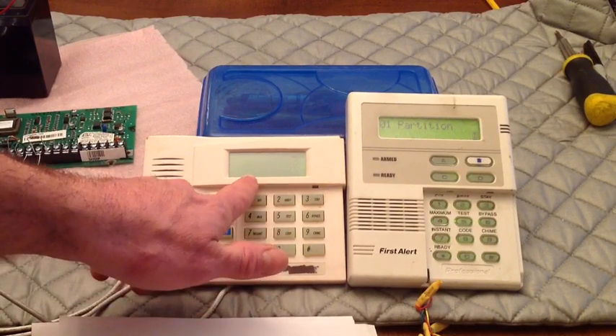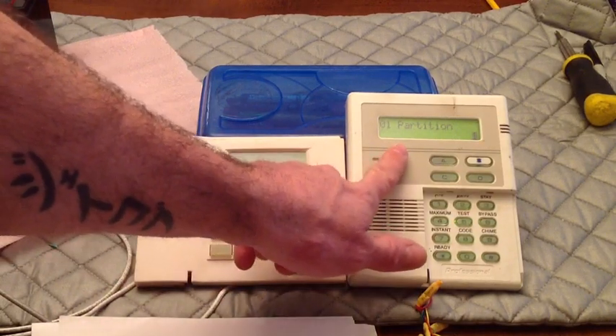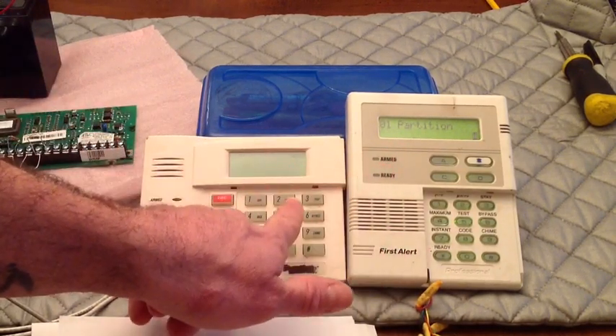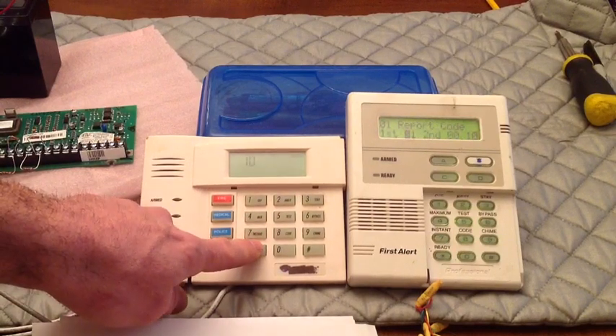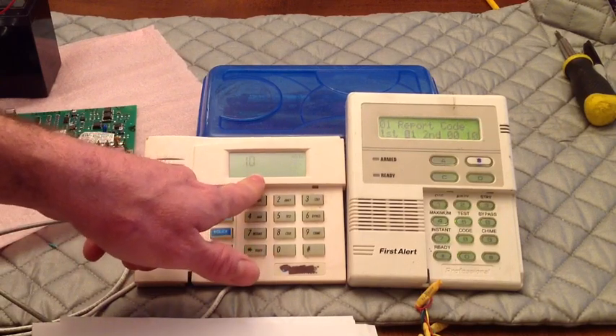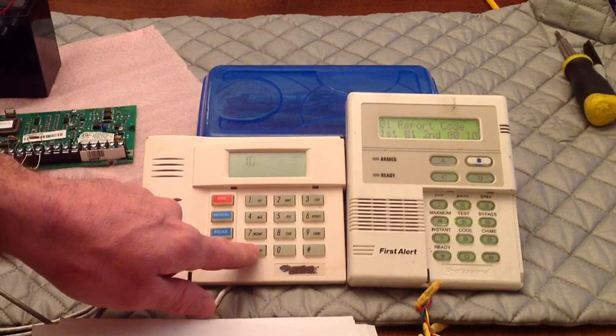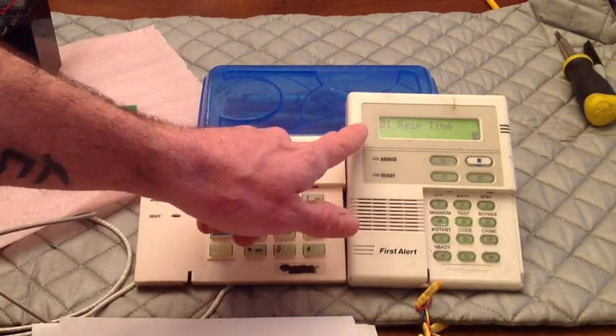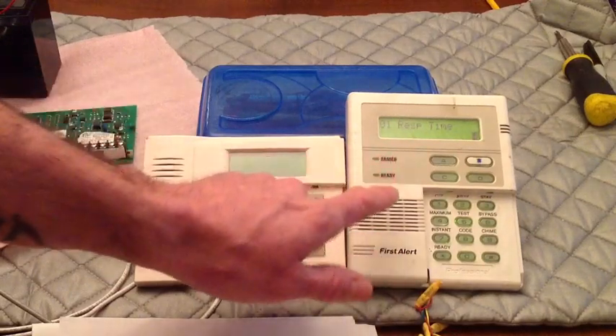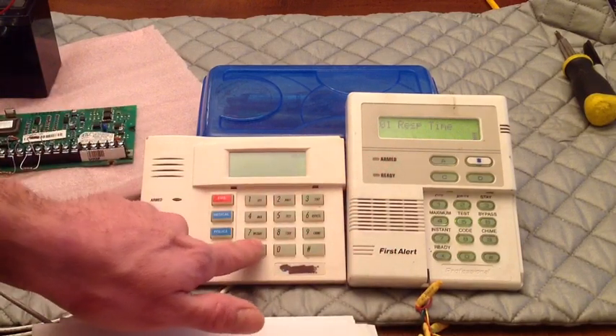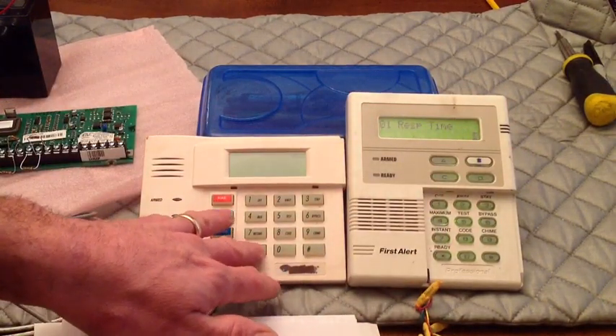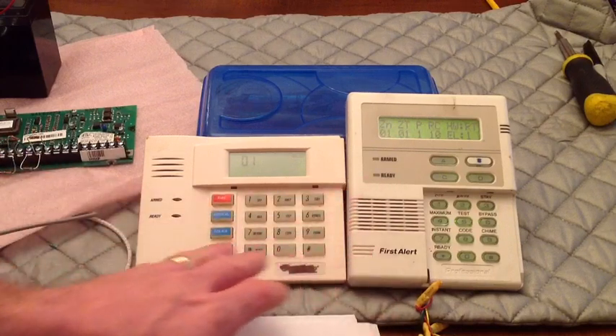Now, the next, after you press star, the next thing you're going to come across is a blank screen. But it's asking for a partition number. You can change that partition number from this keypad. It's just not going to show up here. Hit star. Reporting code is the next thing that shows up. And it tells you right here that your reporting code is 10. You can change that if needed. If you want to leave it alone, just hit star. The next thing that comes up, and now, on the other zones it will ask you for hardware type. But on zone 1, it just goes straight to response time. We can go ahead and just skip past that. We can explain what all these are if needed. But this is just programming. Most of the time, you're going to leave all this default, like in response time and such.